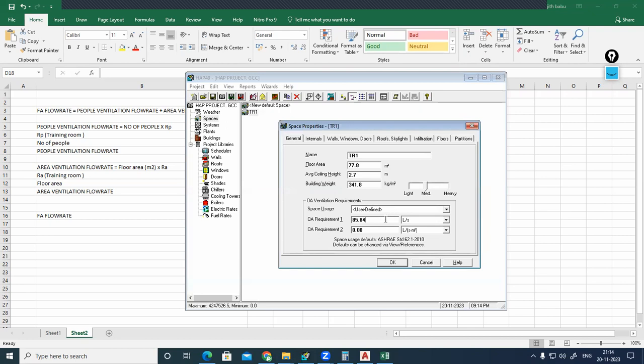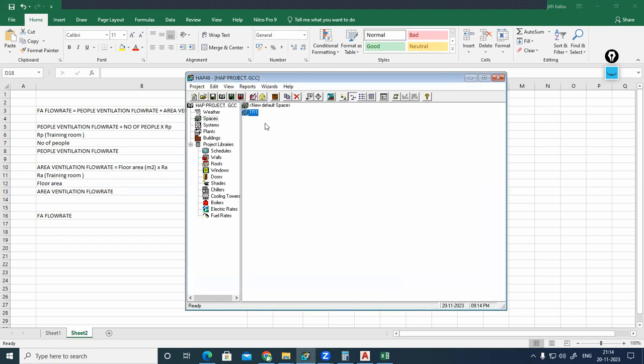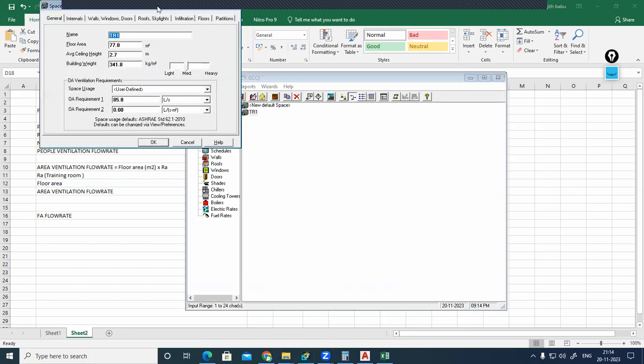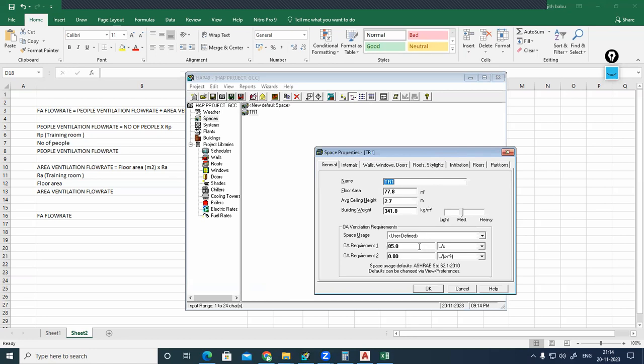85.84 liter per second. You can round that to 85.8. Even if you round that to 86 liter per second, no problem. It's a 0.16 liter per second difference, right? Now click OK. Now when the software calculates, when this 85.8 liter per second of air is introduced inside, the AC machine has to take care of how much sensible load, how much latent load, everything. The software will do the psychrometric calculation in the background. This is where we have given the input manually.